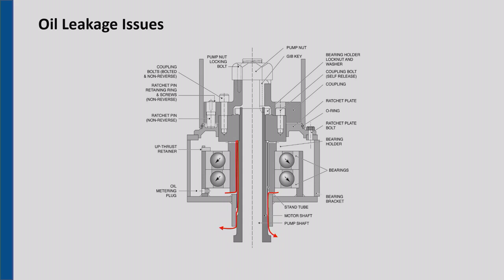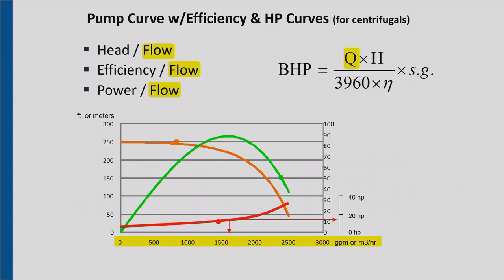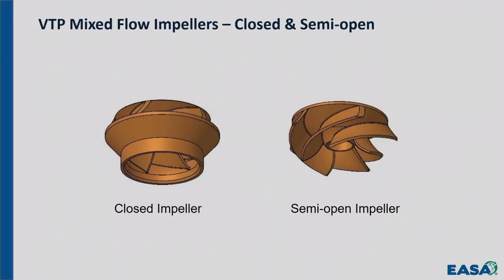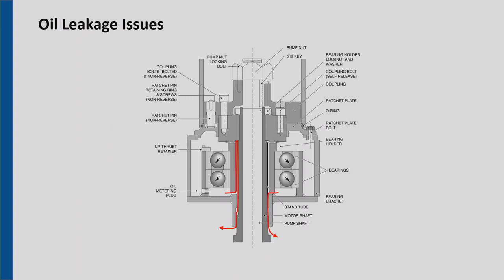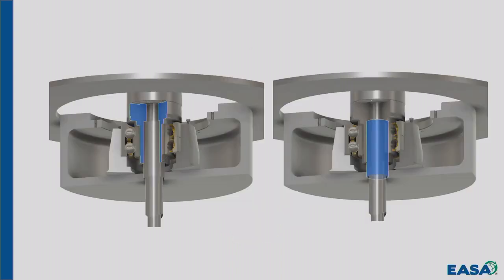Okay? When a pump is running, this lower bearing will pick that oil up and pump it, literally pump it, up into the upper bearing, where it comes out and starts circulating around. So oil levels will be up as high as here in the bearing itself. Okay? To keep that oil from running down inside the motor, there's something called a stand tube, and the stand tube will be right in there. This picture should help clarify that.